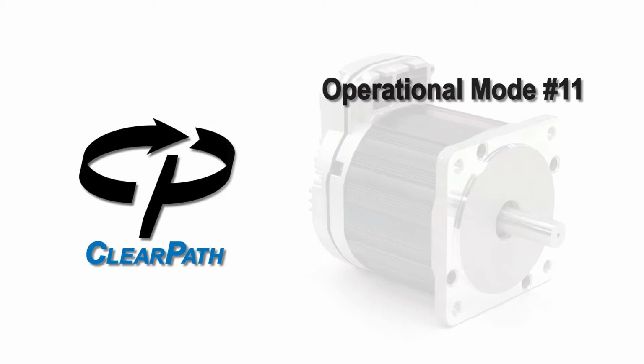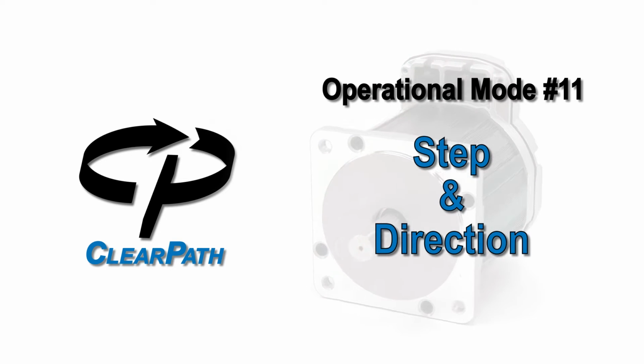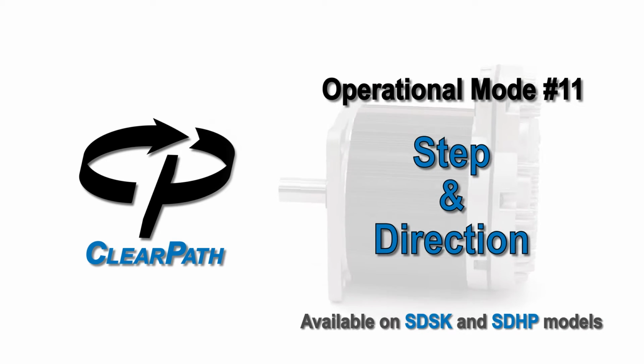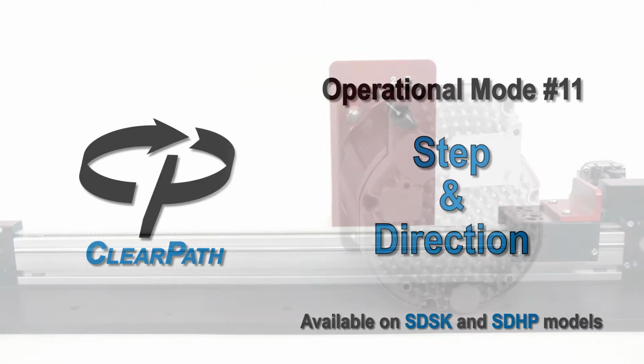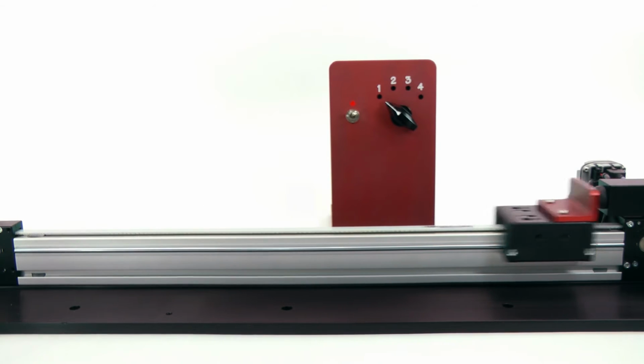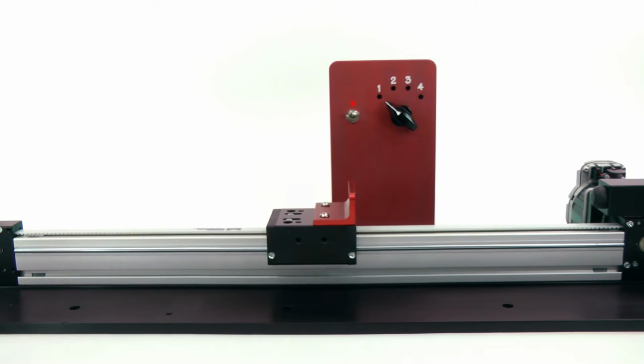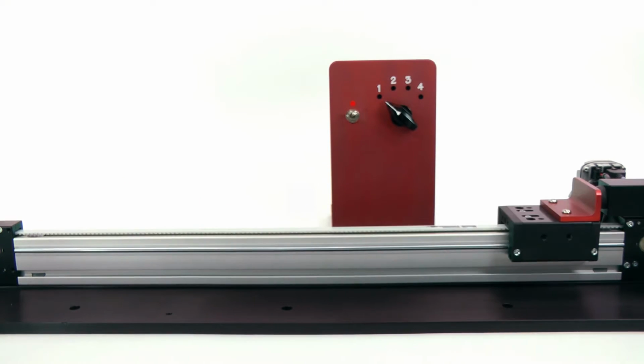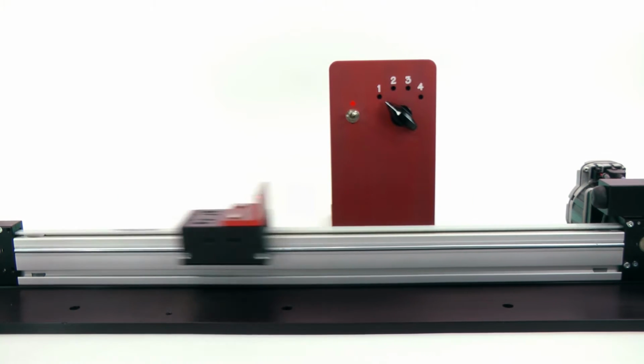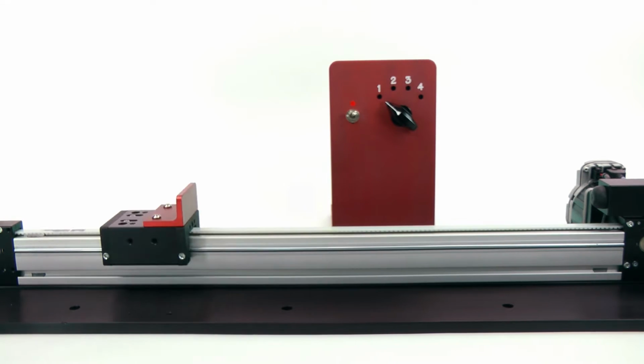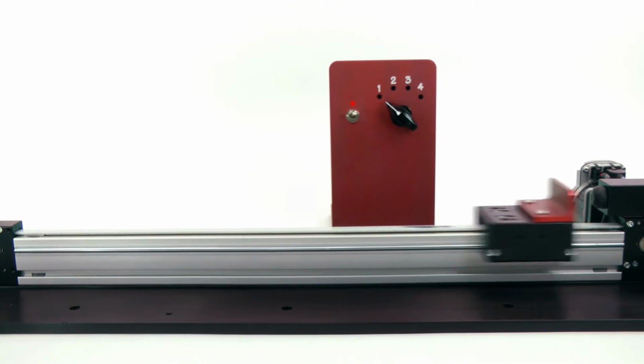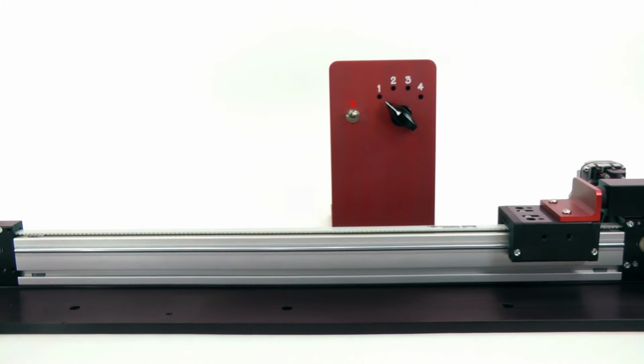ClearPath Operational Mode 11, Step and Direction. Step and Direction is the mode you need when you're going to use a Step and Direction indexer to generate motion trajectories. Many applications can be done with ClearPath's MC models with their built-in motion controller. But for applications like CNC control, or where you already have an indexer and software that you want to keep, ClearPath SD is the way to go.